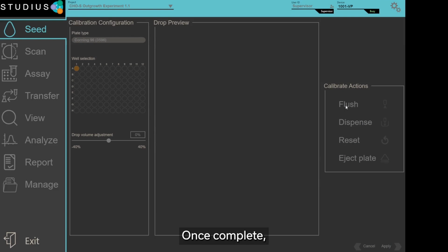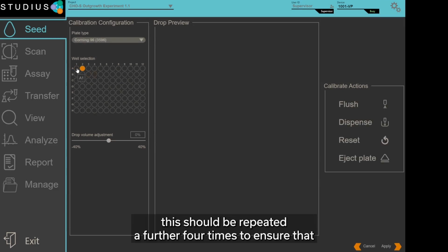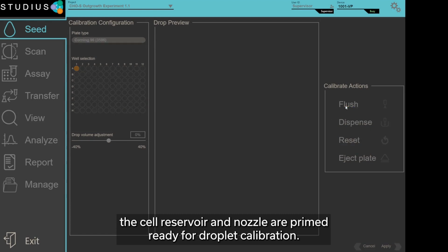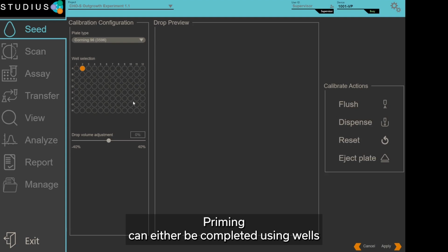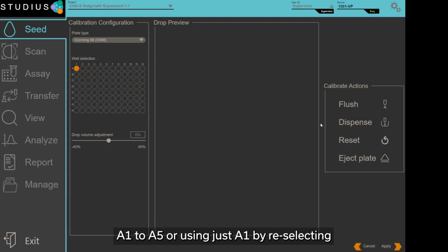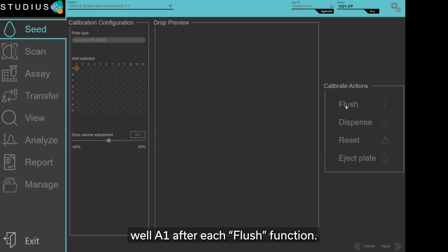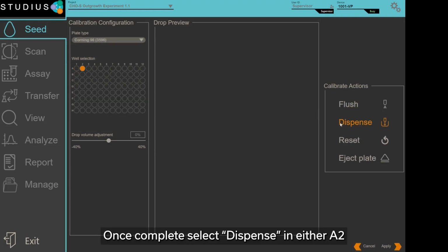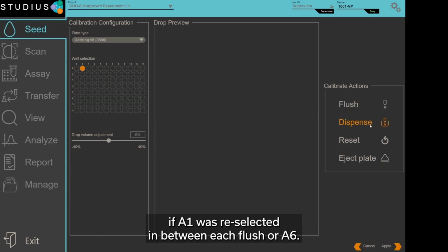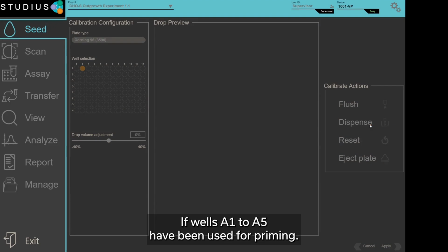Once complete, this should be repeated a further 4 times to ensure that the cell reservoir and nozzle are primed ready for droplet calibration. Priming can either be completed using wells A1 to A5 or using just A1 by reselecting well A1 after each flush function. Once complete, select Dispense in either A2 if A1 was reselected in between each flush, or A6 if wells A1 to A5 have been used for priming.